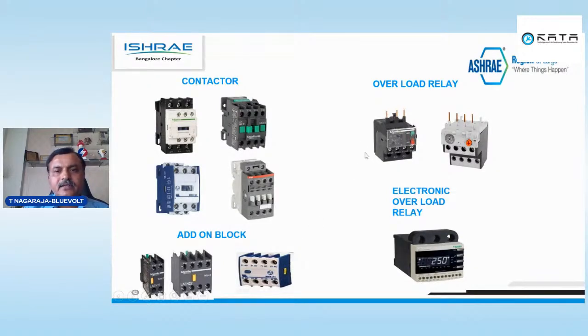Then overload relays. Overload relays are of two types, thermal and electronic, as I told. Thermal relays again take time, 60 to 90 seconds, to trip the contactors. Your thermal contact will break. You have got 4 points, 95, 96, 97, 98. 95, 96 will usually be used for switching off or on, and 97, 98 will be used for alarm purpose. Then electronic will be instant. Whenever overload occurs, 110%, 115%, whatever limit you set, once your motor current crosses it, this will trip instantly.